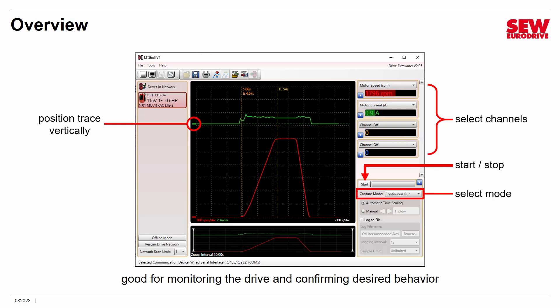The first thing you'll probably want to do is position the traces vertically so you can look at them properly. By default, they're all aligned on top of each other, but if you want to separate them, simply grab the little colored arrow next to each trace and move it up and down on the screen. I've moved my green trace — motor current — above my red trace, which is motor speed. At the bottom of the screen is a little window showing all the captured data. Once data moves out of this window, it's gone forever, so click the Stop button when you have what you need. By moving the vertical lines on the left and right side, you can zoom in on the trace in the larger window above.